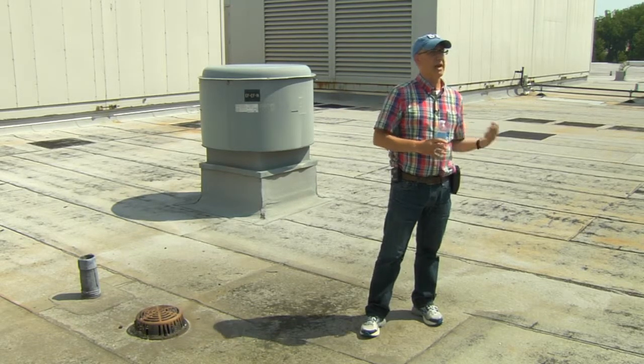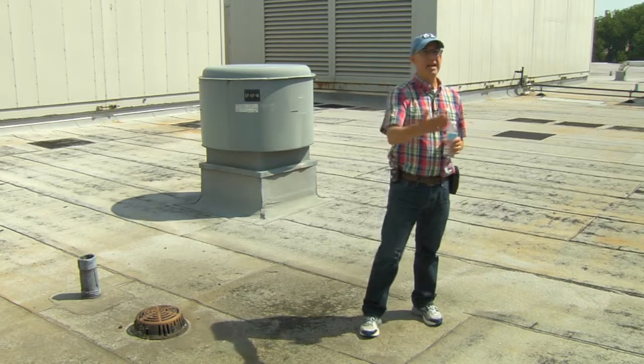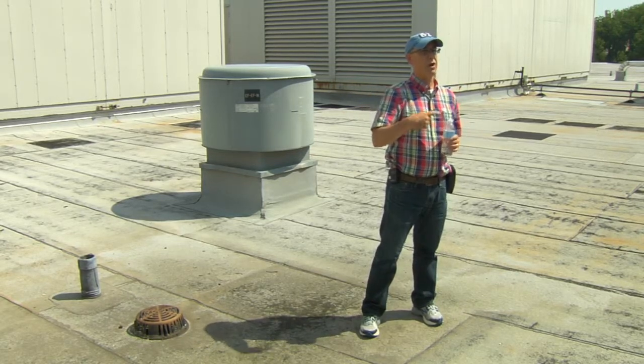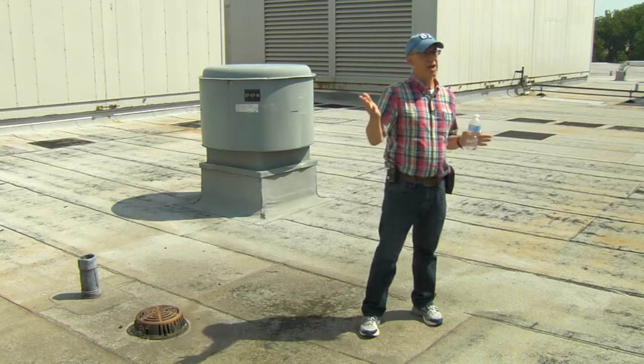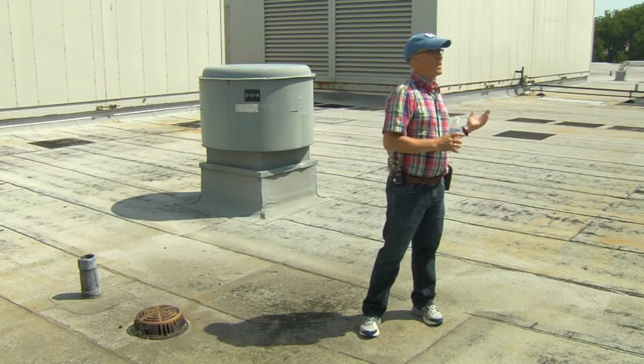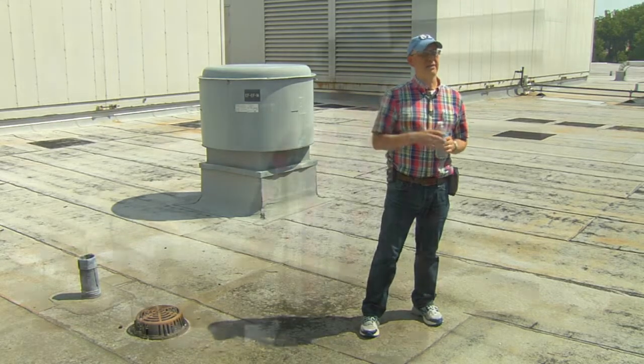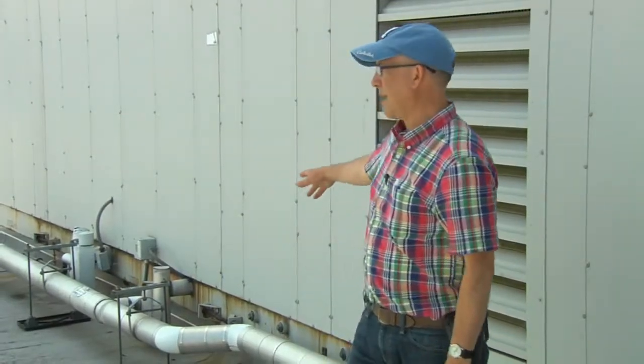Dampers, if we can look at the economizers, we want to make sure that if they're supposed to be on full recirc, that the outside air dampers are not stuck wide open. Those are some of the things that we want to look at. We'll spot check.